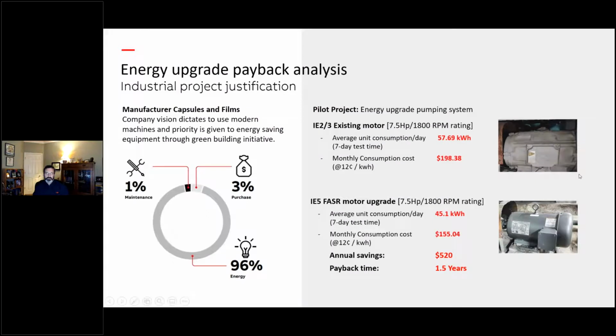And then this was an electrical company in India. They're a manufacturer of capsules and films. And they upgraded a pumping system, a variable speed, variable torque system. So it went from variable speed to variable speed, so it's an equitable comparison. And this is just raw power consumption. So it's not like they went from a fixed speed pump to a variable speed and got savings that way. This was literally variable speed before.